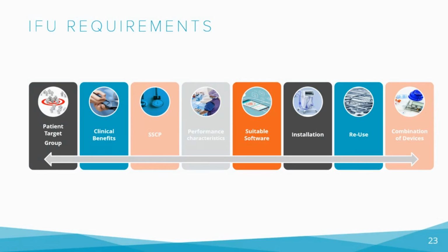In addition to these requirements, the EU MDR also requests that IFUs be regularly reviewed and updated to ensure that they remain accurate and up to date with any changes or new information related to the device. Complying with the IFU requirements under the EU MDR is crucial for medical device manufacturers, as failure to do so can lead to delays in obtaining regulatory approval or even rejection of the device.